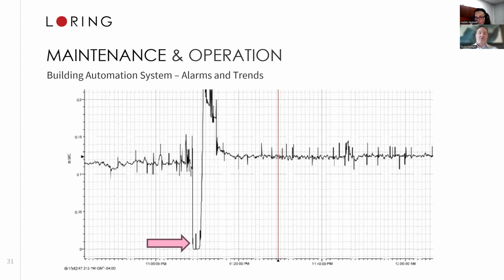You can see at that trough point where the trend line bottoms out to 0, that's indicating that this room did not maintain a differential pressure across this power outage that we had simulated. So trying to figure out why that is like an error point. So the building operating engineers will be able to read a trend like this and then understand, okay, there was a problem in the system. We need to either ourselves troubleshoot it or reach out to outside help in order to help troubleshoot and see why the system is behaving this way.